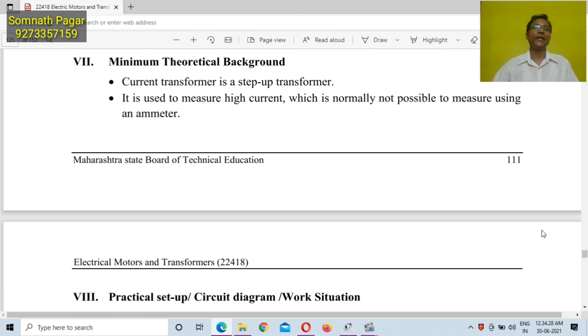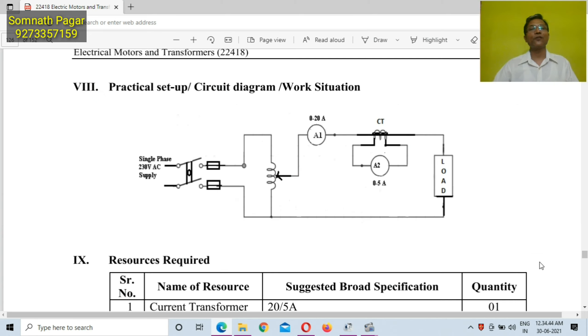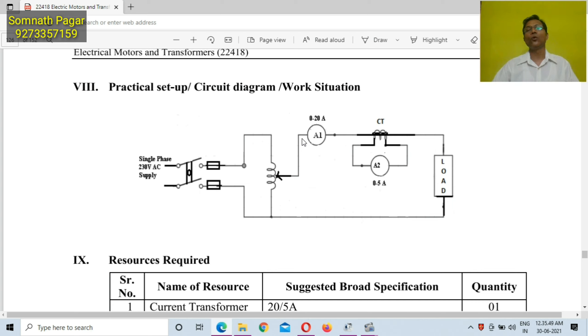You might have seen in substations that CT is connected to an energy meter. In this practical setup, single phase 230V AC supply is connected to a single phase autotransformer. From the autotransformer, the phase is connected to one ammeter A1, which will measure I1. From that ammeter, the phase is connected to the primary winding of the CT.